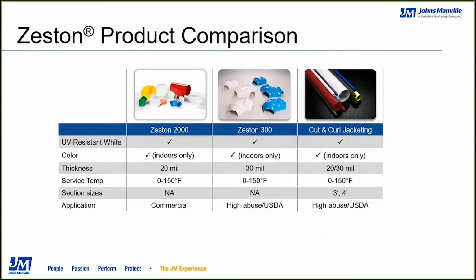Cut and curl jacketing: basically, to create a complete vapor barrier system, the fittings would need to be glued or welded to a cut and curl jacket if it is a fully jacketed system. And again, that is offered in both 20 and 30 mil and in color and white as well. USDA regulations require that in a food processing facility, they require the 30 mil thickness for that rating.